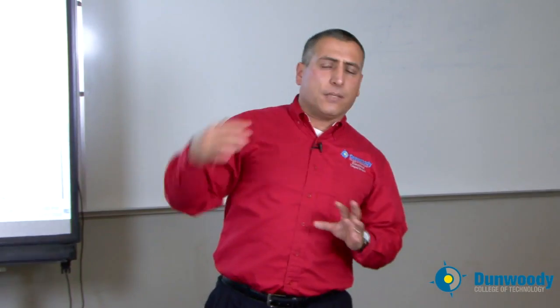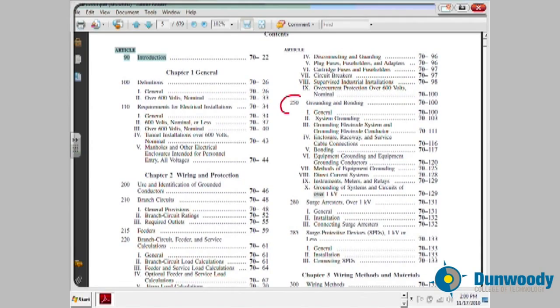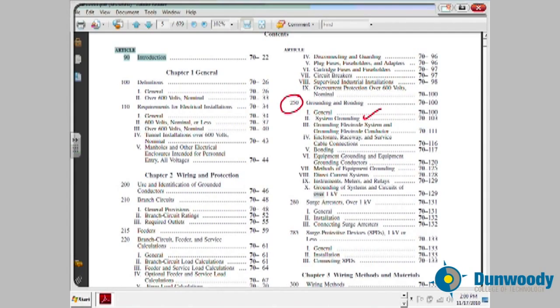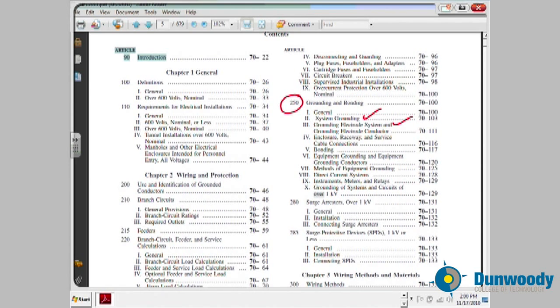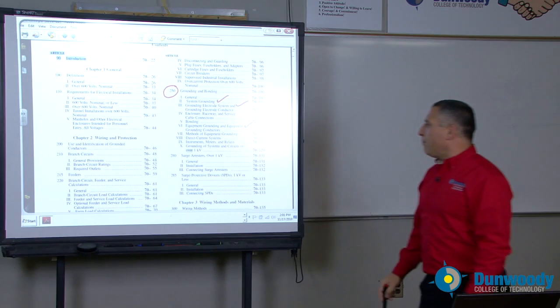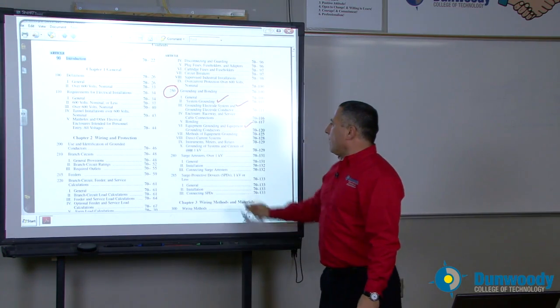Another important topic is grounding. As we bring in service entrance conductors, branch circuits, and feeders, you need to provide a grounding conductor, equipment grounding conductor, grounding electrode conductor, and bonding conductor. All these definitions are in Article 250, grounding and bonding. Is the system grounded or not? Whether it's a Y system, delta system, or single-phase system, we're going to ground it. We size the grounding electrode conductor differently than we size the equipment grounding conductor, and we will be touching on that later on.